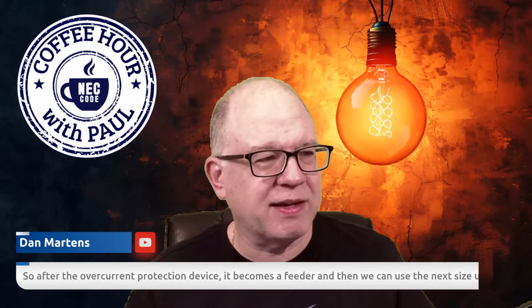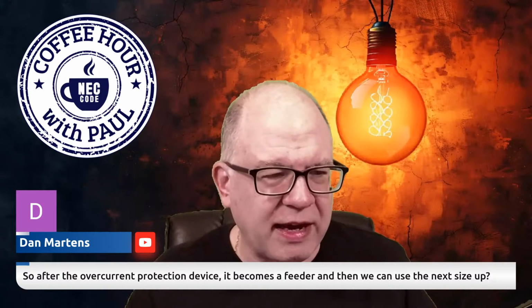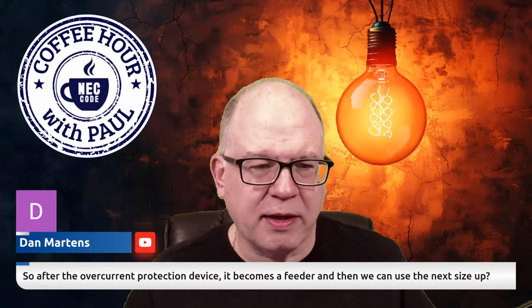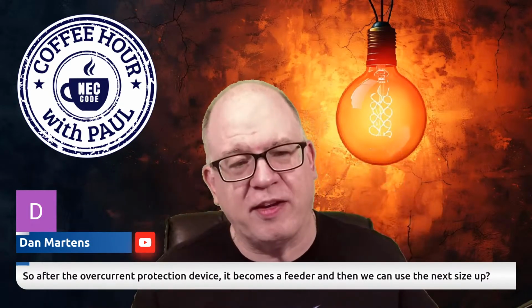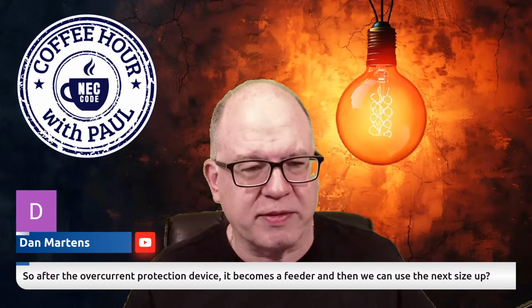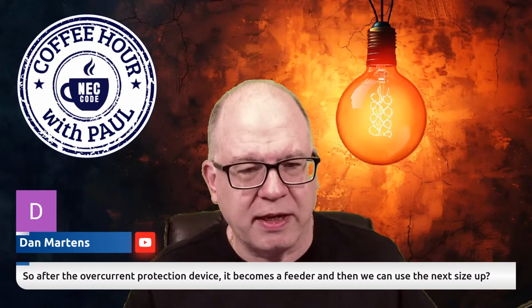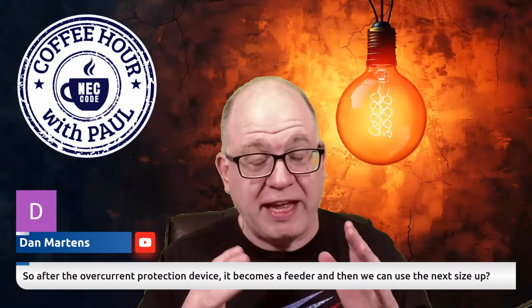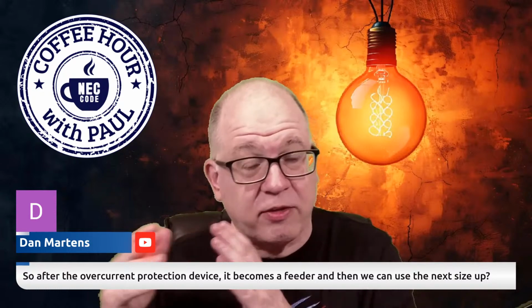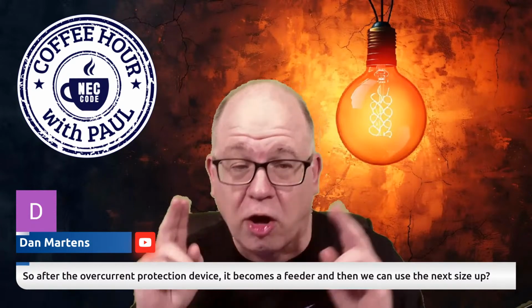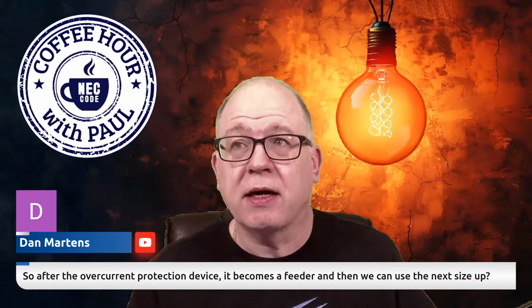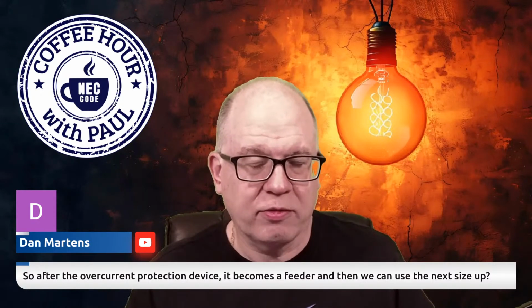Okay. Dan says, so after the overcurrent protecting device, it becomes a feeder. For all intents and purposes, yes. It's on the load side of an overcurrent protected device. But after it comes off of that, if it terminates into a piece of equipment, it could also be a branch circuit as well. Okay, so that type of thing.